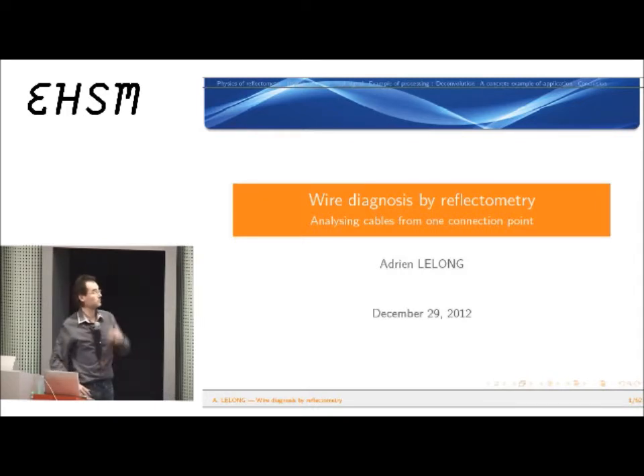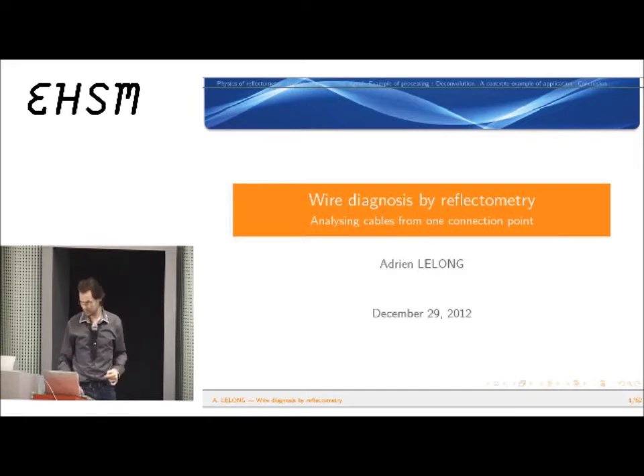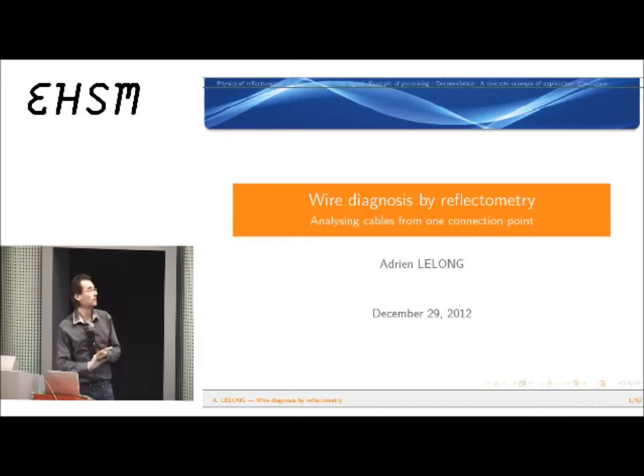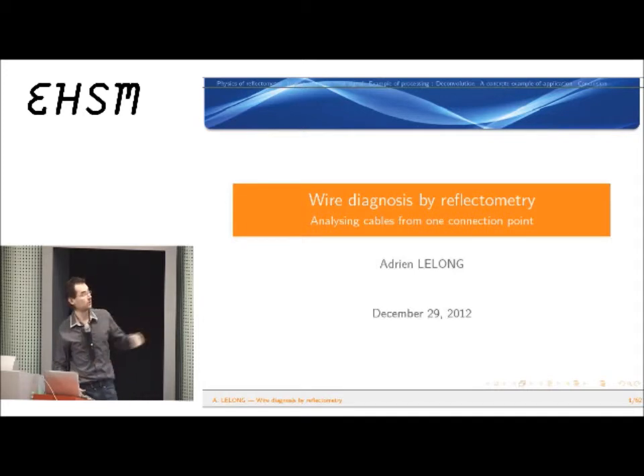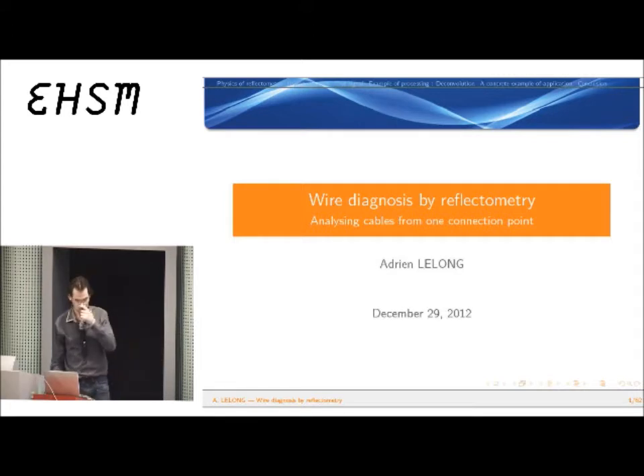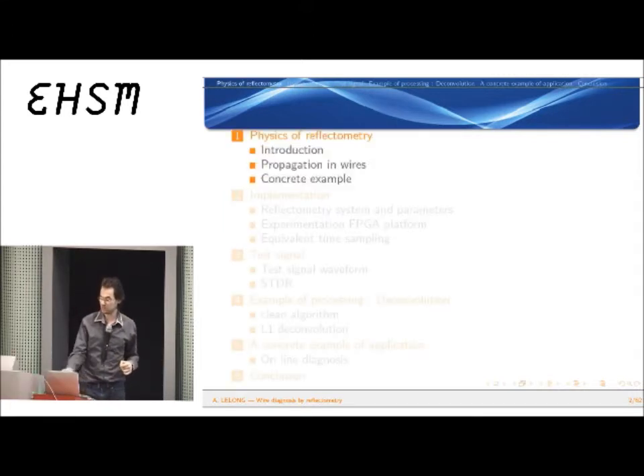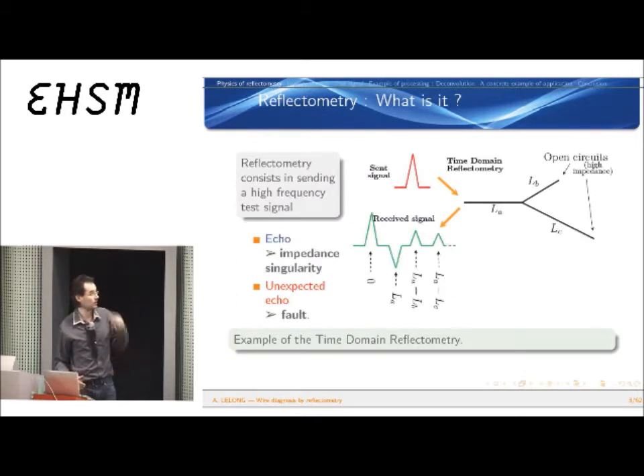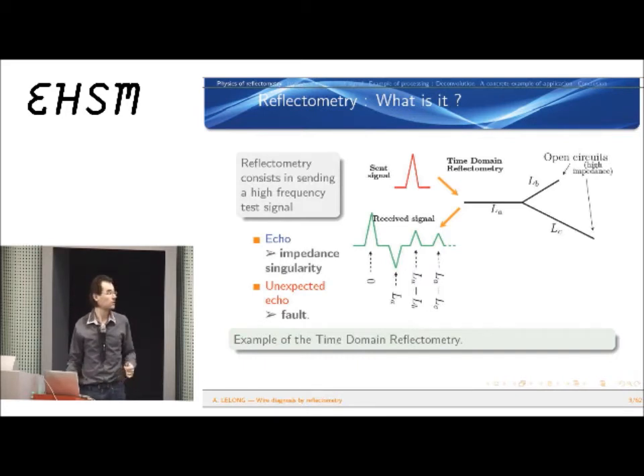I will begin with the physics of reflectometry, just to explain what we are talking about. The principle is very simple: it consists in injecting a high-frequency signal — typically a pulse or similar — into a wire, which reflects on each singularity of the wire. By singularities, I mean junctions, end-of-wire, or changes in the geometry of the wires. We get echoes by measuring the voltage, and by analyzing those echoes, we can know if there are faults corresponding to unexpected echoes.